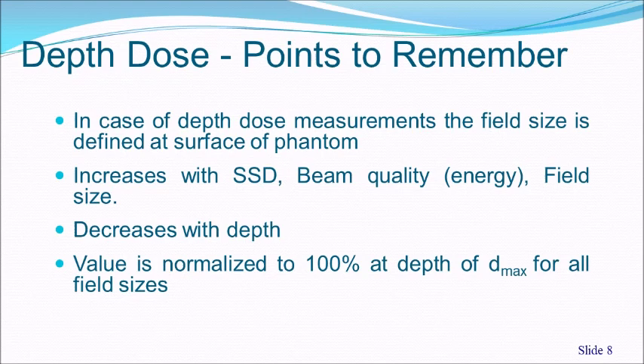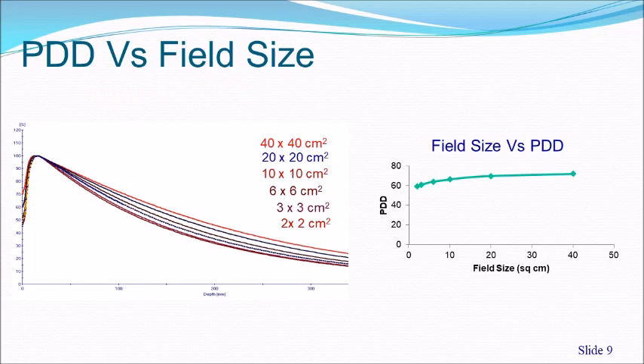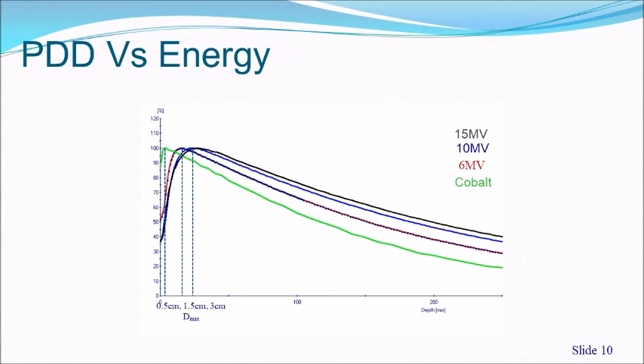Key points for depth dose: the field size is defined at the phantom surface. PDD increases with SSD, beam quality (higher energy means higher penetration), and field size, but decreases with depth. The value is normalized to 100 at D-max. PDD curves for various field sizes from 2×2 to 40×40 show that PDD increases with field size and then reaches a saturation level for very large fields.